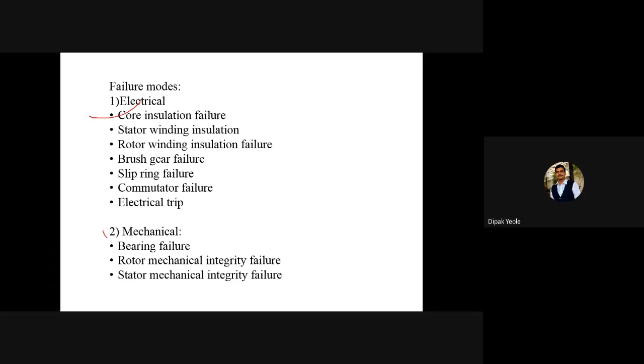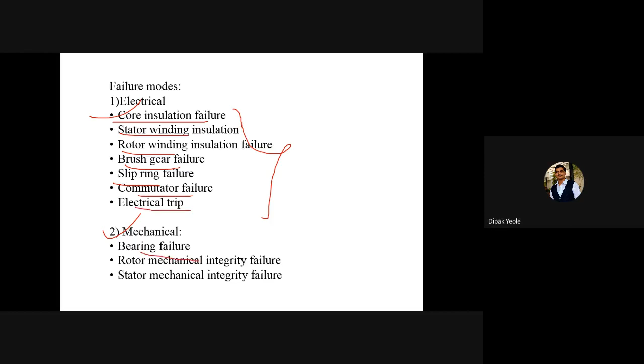And second is the failure mode. I have divided the failure mode into two types, the electrical mode and mechanical mode. The electrical mode involves electrical parameters: the core insulation, stator winding insulation, rotor winding, brush gear, slip ring, commutator failure, and electrical trip. On the mechanical side, we are interested in the bearing fault, the rotor mechanical integrity, and stator mechanical integrity. Now there is a difference between preventive maintenance and condition monitoring.